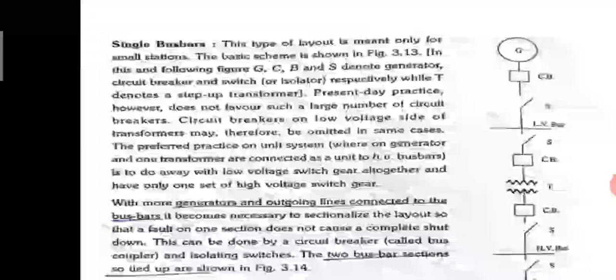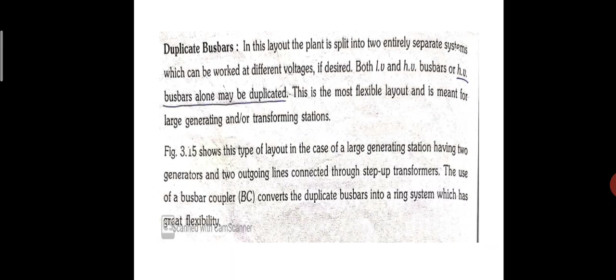And second one, duplicate bus bars. In this layout, the plant is split into two entirely separate systems which can be worked at different voltages. If desired, both LV and HV bus bars or HV bus bars alone may be duplicated. This is the most flexible layout and is meant for large generating and transforming stations. This layout is shown for a large generating station having two generators and two outgoing lines connected through the step-up transformer. The use of a bus bar coupler converts the duplicate bus bar into a ring system which has great flexibility.